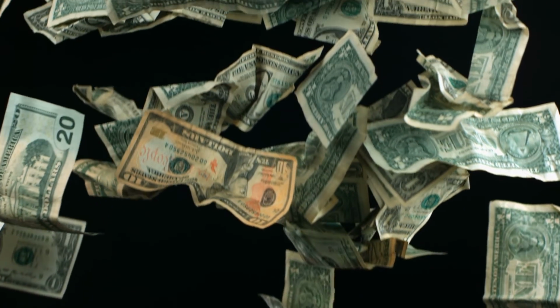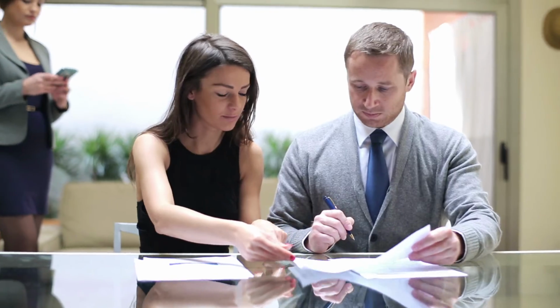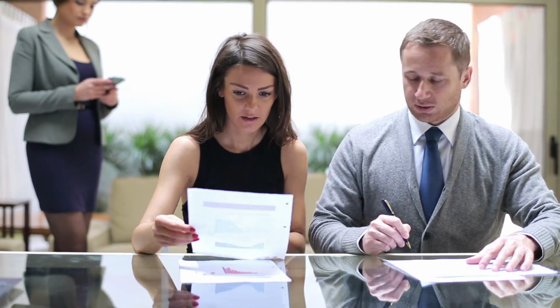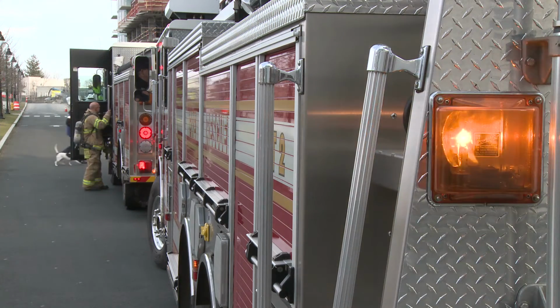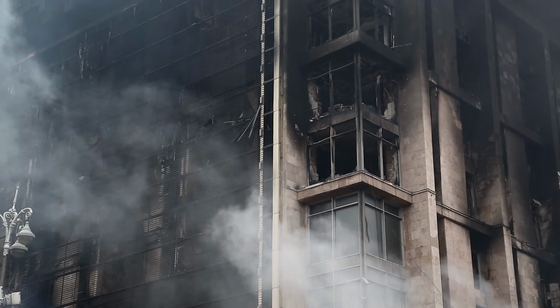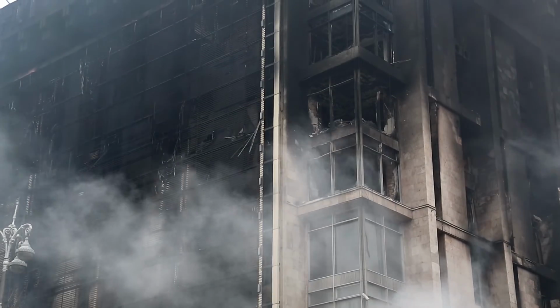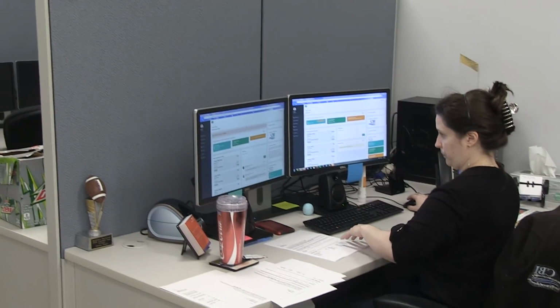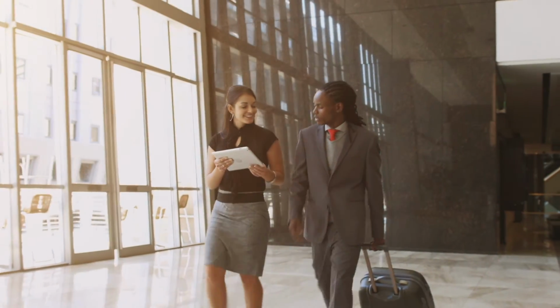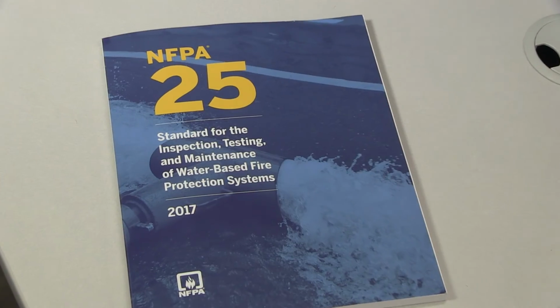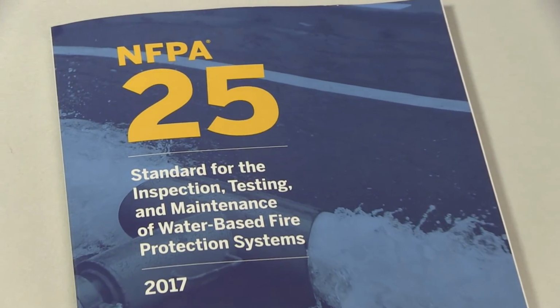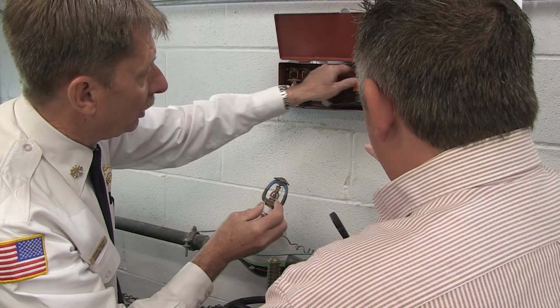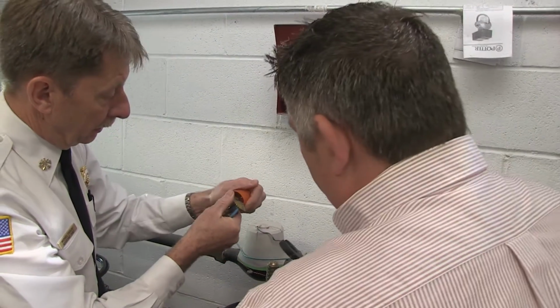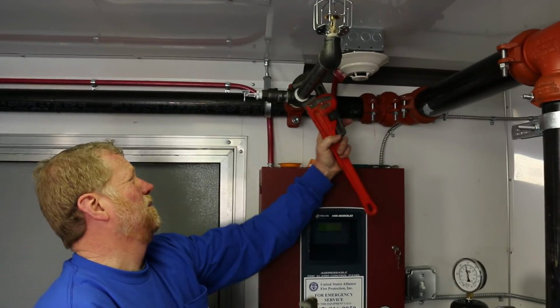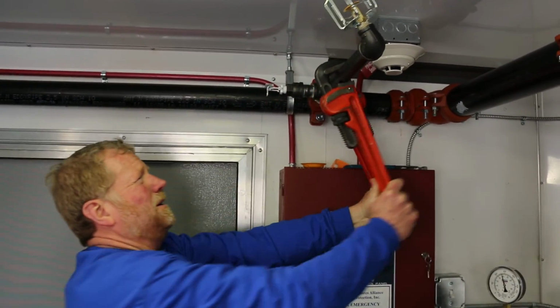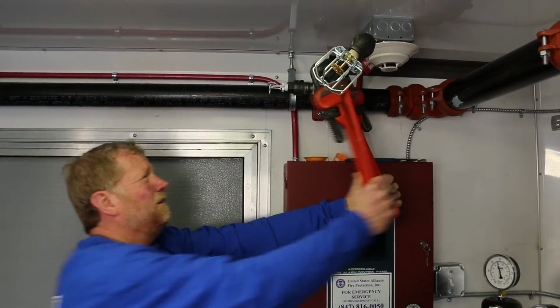In addition to the life and property benefits of a properly inspected, tested, and maintained fire sprinkler system, you can also benefit from insurance savings. However, when you don't perform ITM of your fire sprinkler system for a number of years, you can lose those insurance savings and put your occupants at risk of a fire. By properly following ITM procedures, you are ensuring a reasonable degree of protection for the people in the building and the property itself. When it comes to ITM, it doesn't have to be difficult. If you as a building owner or manager follow the NFPA 25 procedures outlined in this video, your knowledgeable NICET Level 2 certified fire sprinkler contractor and/or certified sprinkler fitter will ensure your building complies with the remainder of the standard and Illinois State Code.